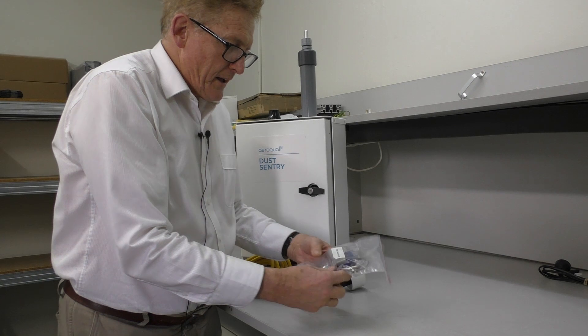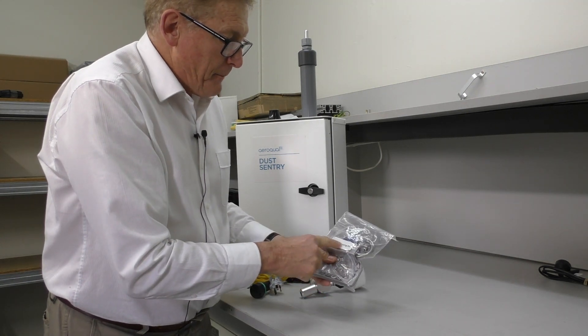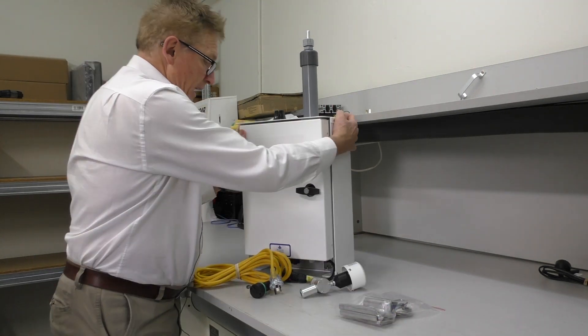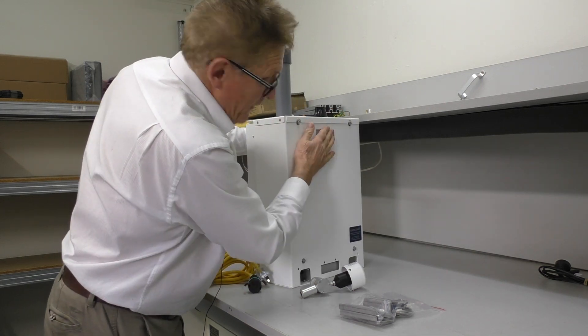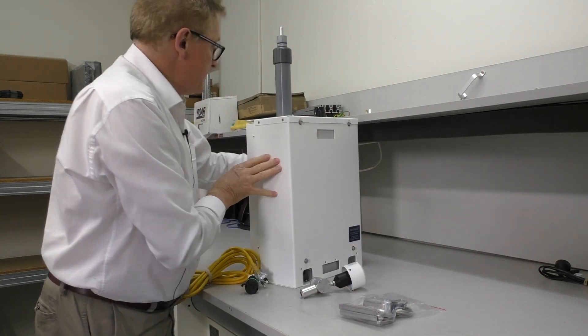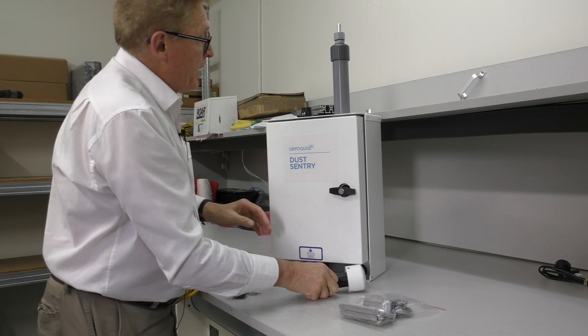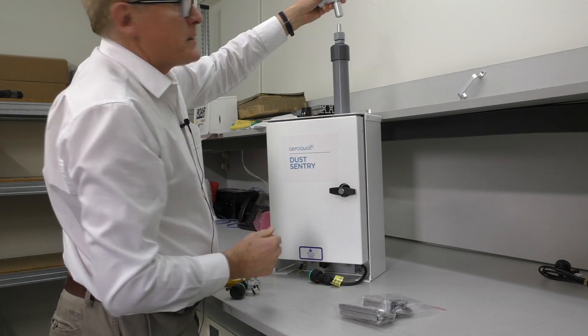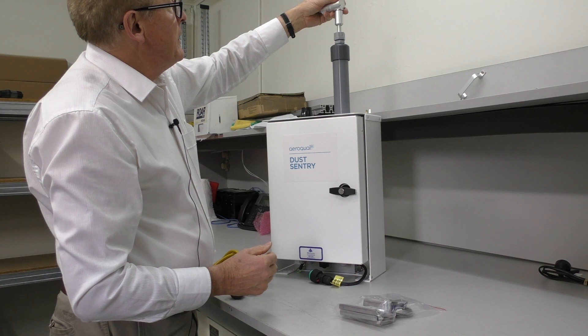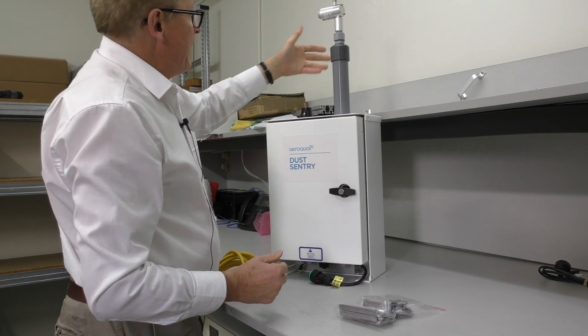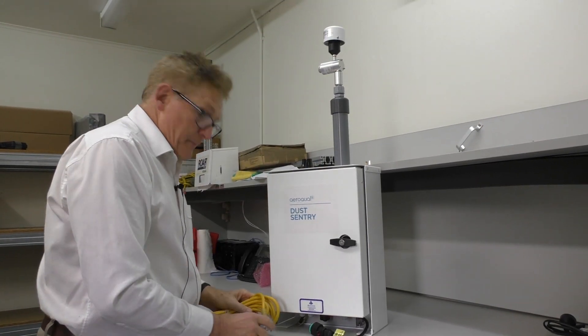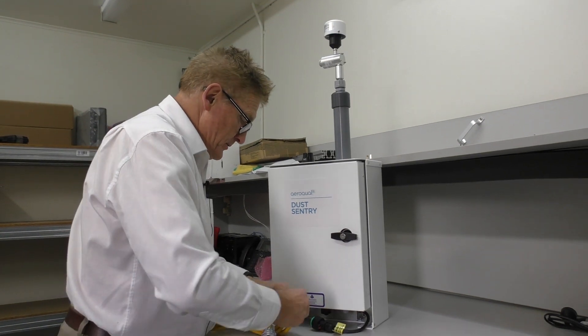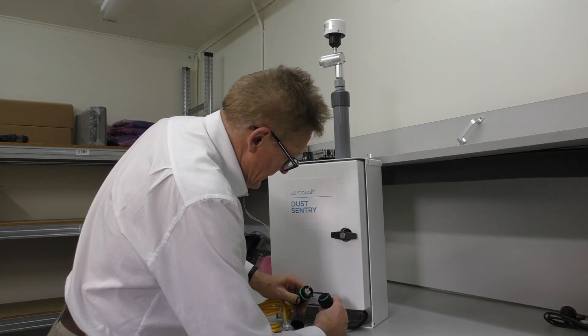Typically you'd be putting a 50mm mounting pole using this mounting kit. You simply hang the instrument on these clips, very easy. All we do, here's our Cyclone. We simply mount that on top, connect the AC power to it.